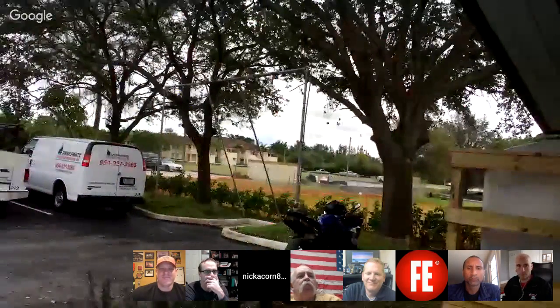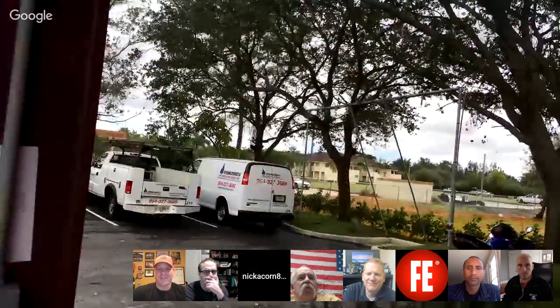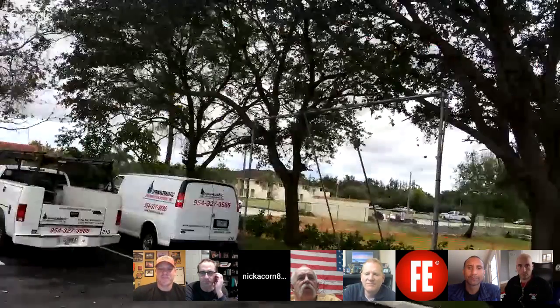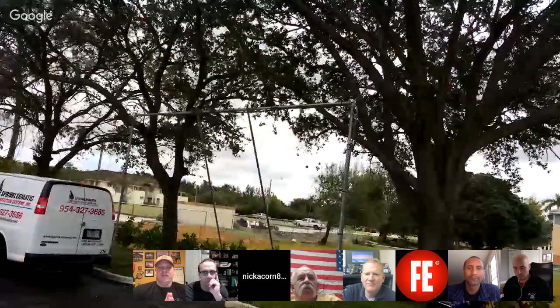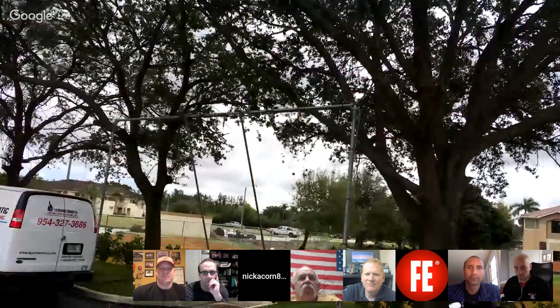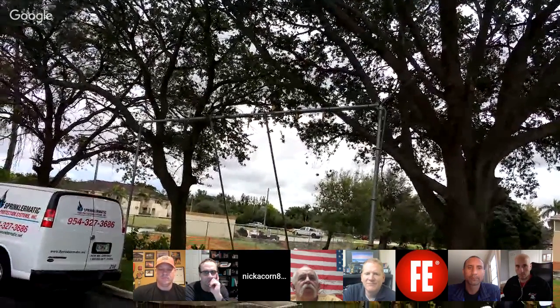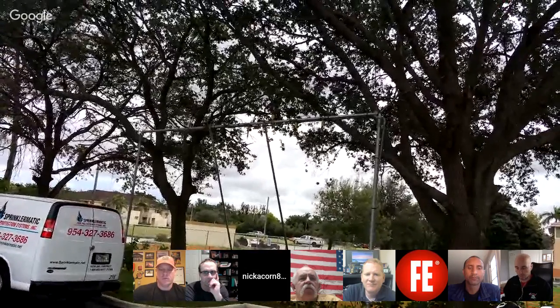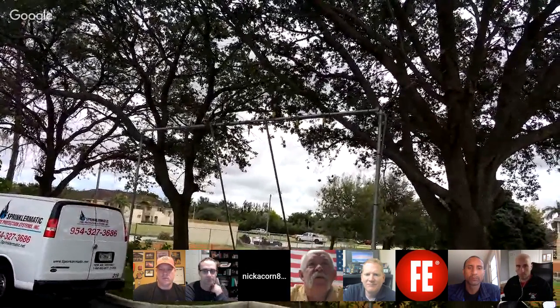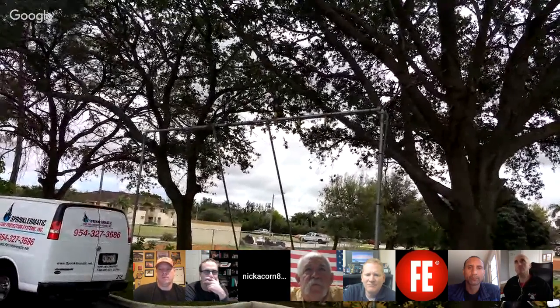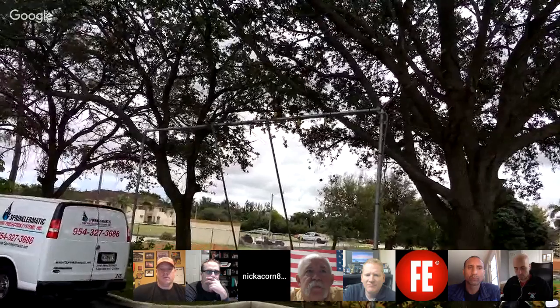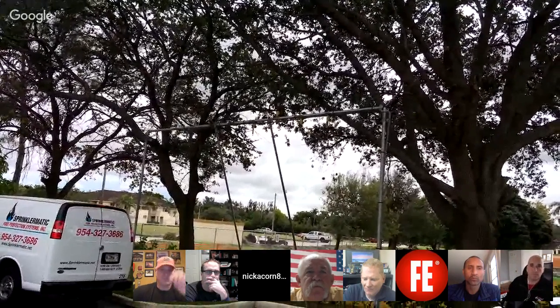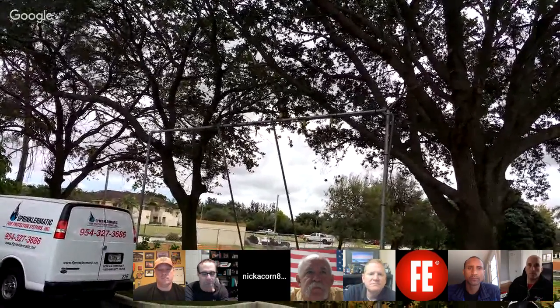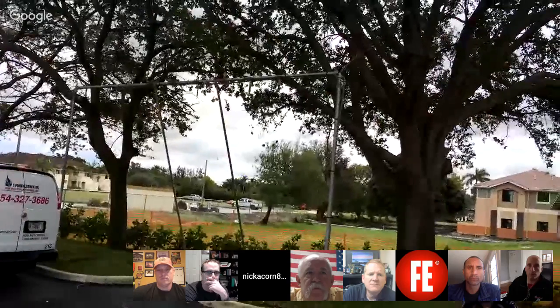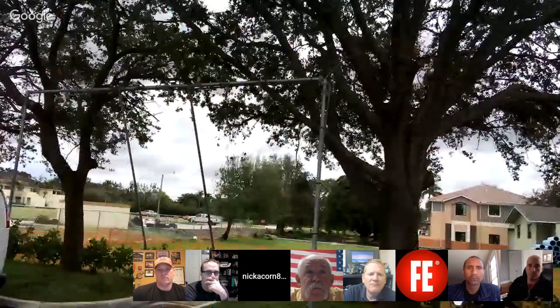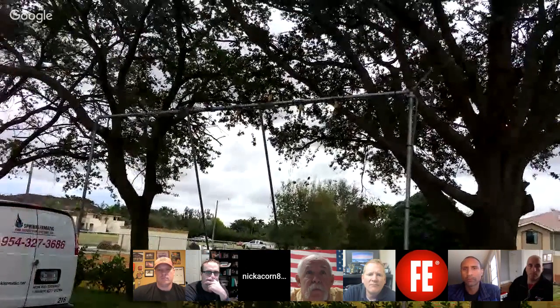So what we see out here is we've created a test bench. And that test bench, why don't you go out there so you can see them. And we're using solenoids outside of their listing. So we've got 24-volt solenoid valves basically attached to a water supply on the discharge side of the fire pump. And then we're activating sprinkler heads to show different spray patterns with 8 different types of heads. We've got the number 1 valve all the way to your left. We're simulating a quick response 5.6 pendant sprinkler head. The second is an upright, same K factor. Then we use a 5.6 horizontal sidewall. We show you a 4.0 horizontal sidewall, 4.9 a residentially listed sprinkler head, just showing the different spray patterns.